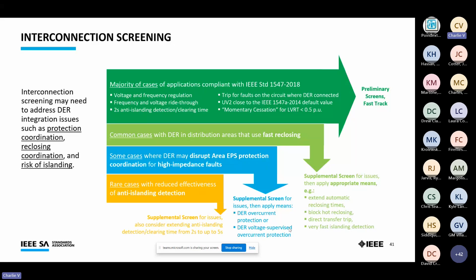A comment on the outlook for interconnection standards: a real appealing progress point on the standards front is the publication of a transmission interconnection standard for inverter-based resources - that's IEEE 2800-2022. Fortunately, there is strong consistency, if not outright matching, in some of the key terminology and how it's defined and measured between 2800 and 1547-2018, terms like cease to energize versus trip, and the maximum rate of change of power output, consistent between the two.